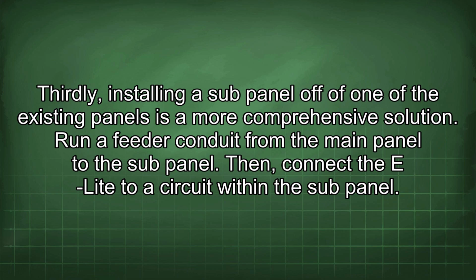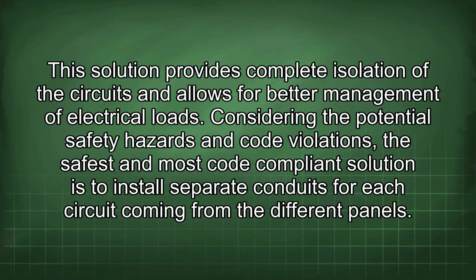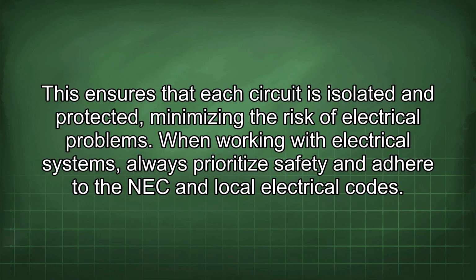Thirdly, installing a sub-panel off of one of the existing panels is a more comprehensive solution. Run a feeder conduit from the main panel to the sub-panel. Then connect the E-light to a circuit within the sub-panel. This solution provides complete isolation of the circuits and allows for better management of electrical loads. Considering the potential safety hazards and code violations, the safest and most code-compliant solution is to install separate conduits for each circuit coming from the different panels. This ensures that each circuit is isolated and protected, minimizing the risk of electrical problems.